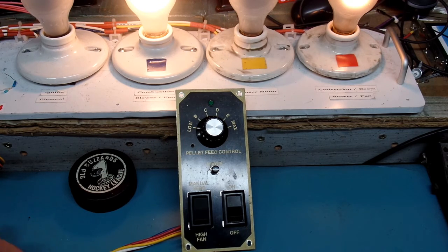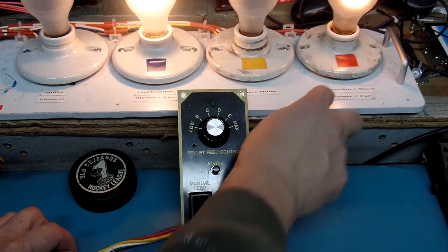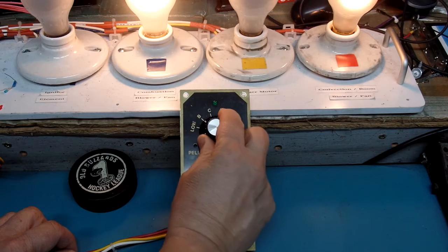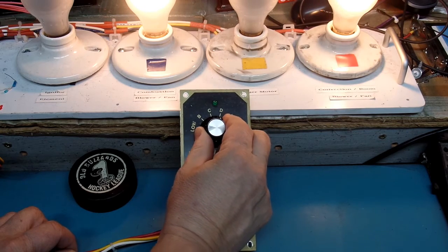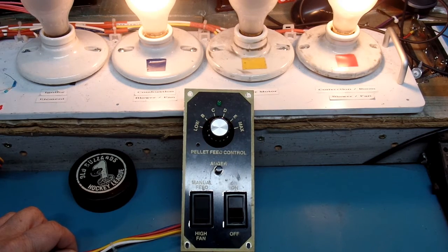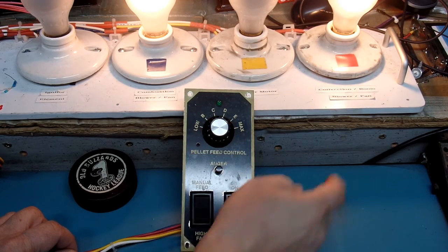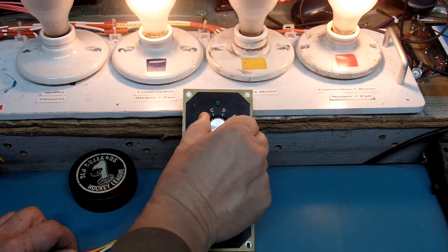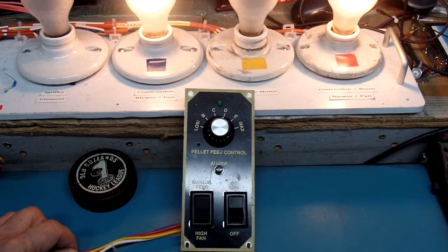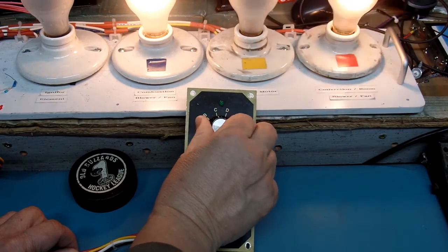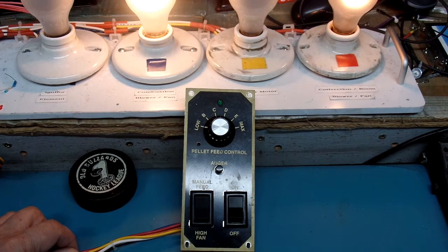The last thing I can do in this manual mode is go through the low, B, C, D, E, max switch positions, and as I do that, the intensity of the convection or room fan will increase and decrease. So B, C, D, E, and max. Notice, as with all controllers of this type, D, E, and max have no effect on the speed of the room fan. They are wired together on the controller, and that cannot be changed. But C, B, and low do have an effect. So there's 4 different speed positions. I'll leave it on low. So that's it for the manual side of the controller.